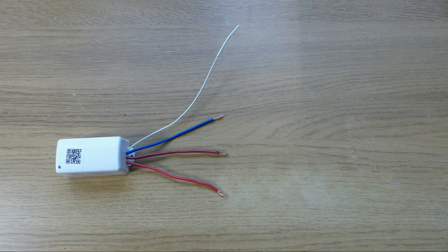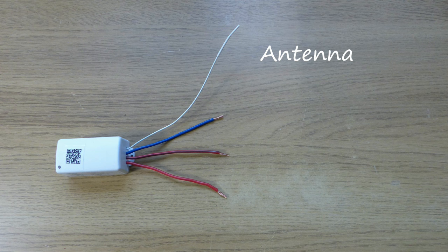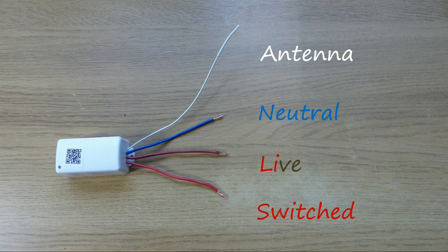The receivers are designed to switch mains powered lighting circuits between 110 and 250 volts AC 50 or 60 hertz. There are four wires. The thin white one is the antenna or aerial. The blue wire connects to the neutral. The red and brown wire connects to the live. And the red wire is the switched output that connects to the lighting circuit.